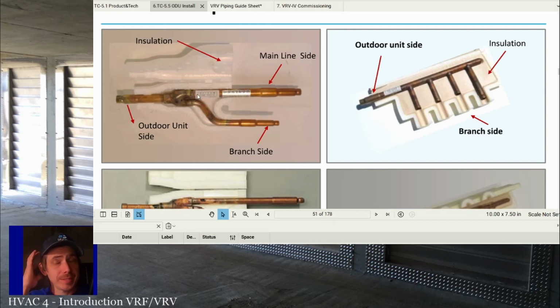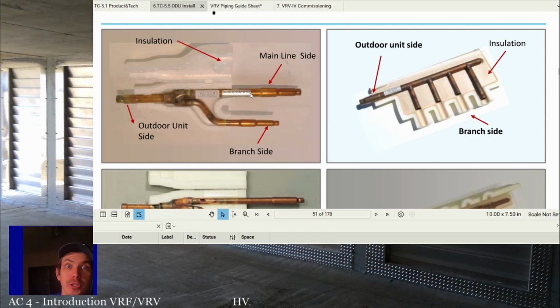And what you do with these things is you cut this pipe at whatever size you need it. So if this is 7/8 and you need a 7/8 connection, then you cut this Y kit right here and you shove your 7/8 pipe in there and you braze it while purging with nitrogen. Okay. You basically just pick your pipe size off of this. And if your pipe size isn't there, you might have an extra reducer that they shipped you in the bag that you have to tie in.